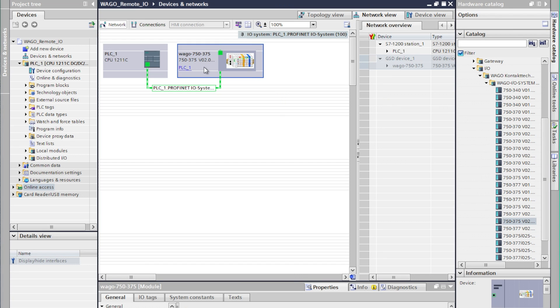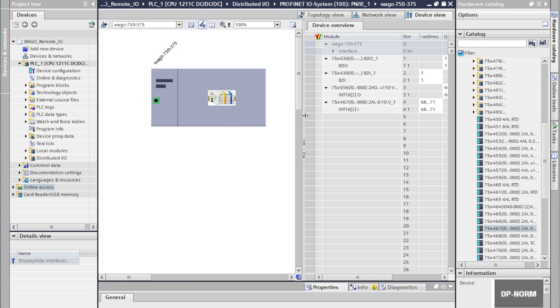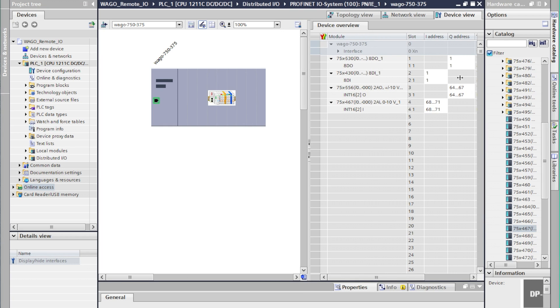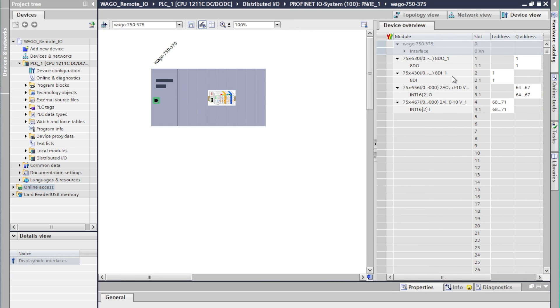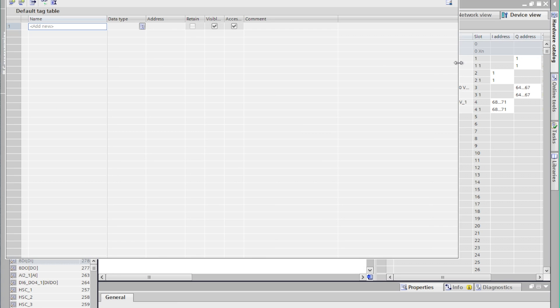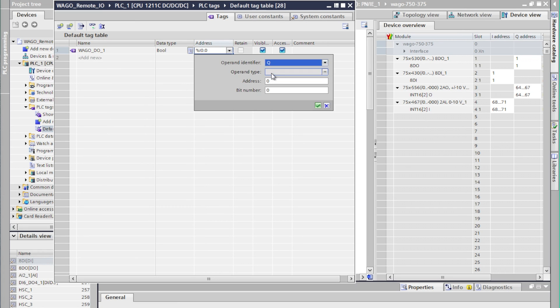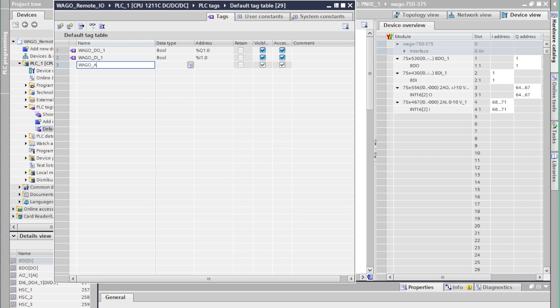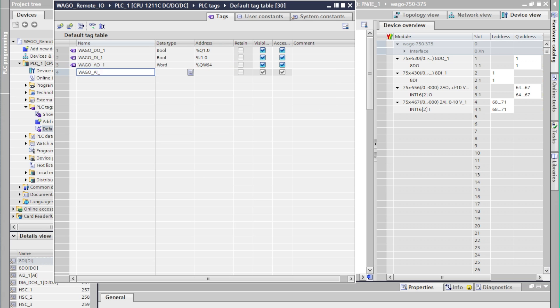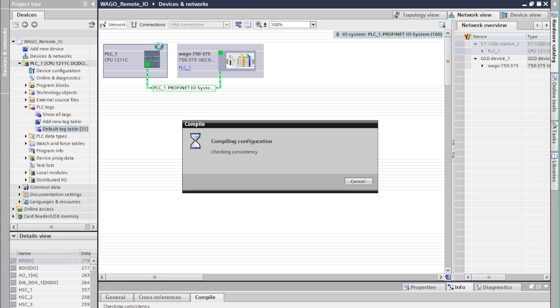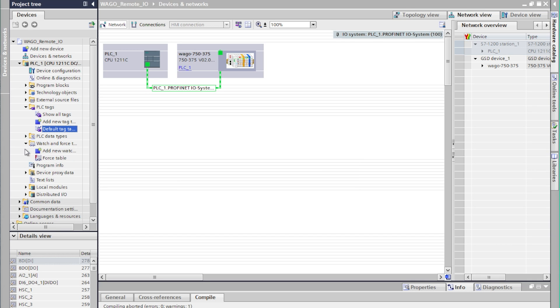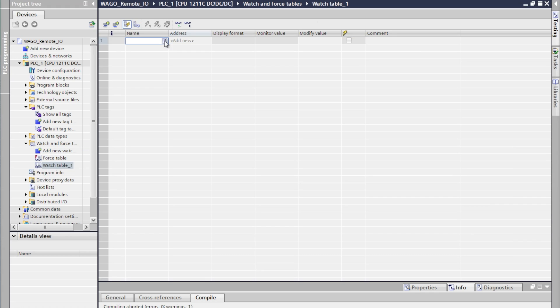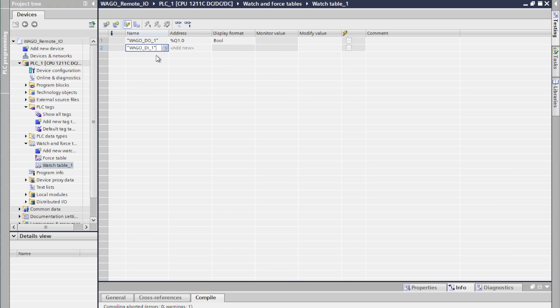Now our communications are all configured and the system is ready to go online however we don't have any way to test it so we're going to quickly create a tag table and tag some of these inputs and outputs so that we can watch them in a watch table and force the values. Now we'll select add new watch table and we'll add all of the tags that we created in our tag table.